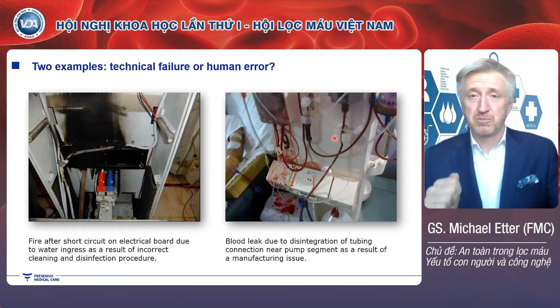This was a relatively small blood loss because the safety mechanisms in the dialysis machine worked properly. So there was an immediate detection of that blood leak and the pump stopped. You see here the venous clamp. That clamp closes and stops the blood pump and prevents the blood leak from creating a substantial blood loss. So here the learning is, yes, there is always a residual risk. We can have issues, but there is also technology built into today's devices that help to reduce the risk if such a technical problem occurs.